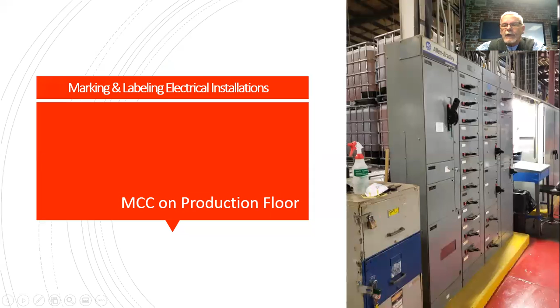This is an MCC located out on the production floor. This is an older methodology, and it's not improper, but you need to recognize that not only are your qualified electrical people working on it at risk, the people working in the area are at risk. And if it's a travel aisle from other locations within the facility, those people are at risk too.